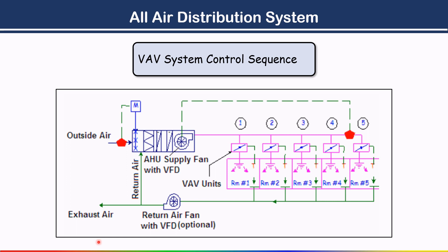As the terminal boxes open and close, the static pressure in the ducting increases and decreases. This change in pressure is sensed by the VAV controller, which reacts to vary the air delivered by the unit. The AC drive controls air volume by keeping duct pressure constant. The pressure sensor is located at the most remote point of the supply main duct — between room 4 and room 5, the farthest point from the AHU.